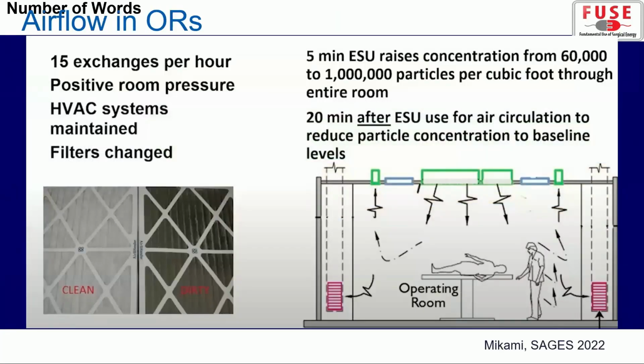So the airflow systems in the OR are regulated pretty harshly. They're mandated to have 15 air exchanges per hour, which means one every 4 minutes. It's usually positive room pressure, where they push air into the room, and then the old air in the room gets pushed out of these vents. HVAC systems have to be maintained, and the filters have to be changed. 5 minutes of electrosurgery raises the concentration from 60,000 to 1 million particles per cubic foot through the entire room. And because 15 exchanges per hour means there's an exchange of air in the room every 4 minutes, they say after 5 cycles it usually should be enough to eliminate the polluted air from the surgical smoke within a room.